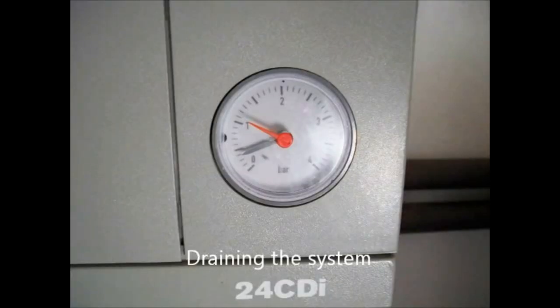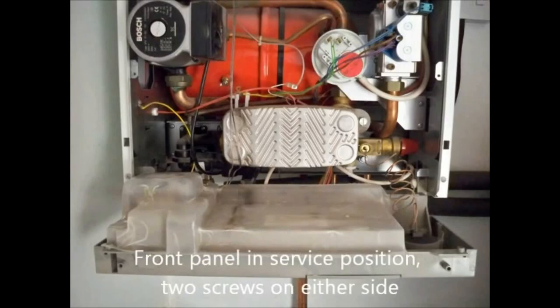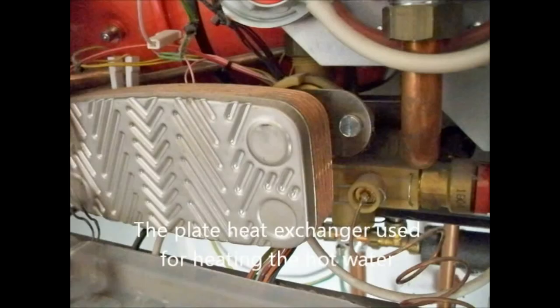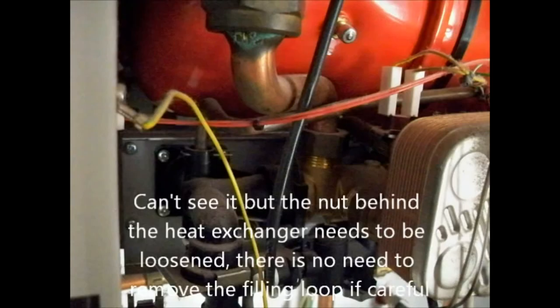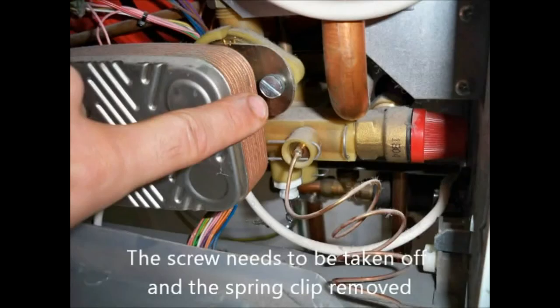Draining the system. Front panel in service position, two screws on either side. The plate heat exchanger used for heating the hot water. Can't see it, but the nut behind the heat exchanger needs to be loosened. There is no need to remove the filling loop if careful. The screw needs to be taken off and the spring clip removed.